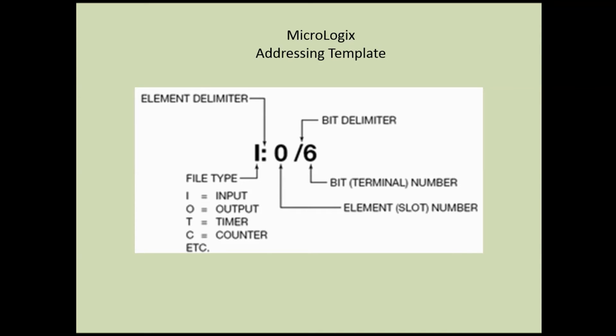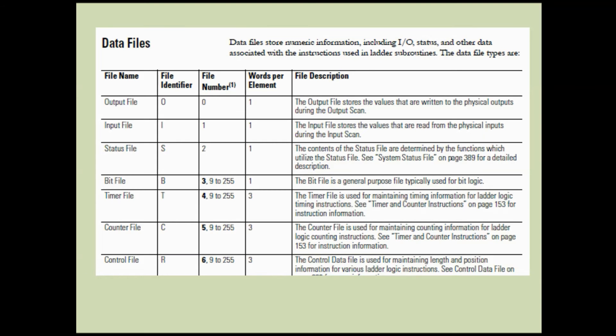When you have an input, you wire it into a module or input card, and the location for that information is I. The next number is the actual slot number. When you look at a PLC you have your power supply, your controller, and then the rest of your cards. Each of those cards has a slot number. In this instance we're using zero - if we have a power supply, the CPU, and then an input card, we say that's slot zero. Then you have a slash followed by the actual terminal number to which the input is wired.